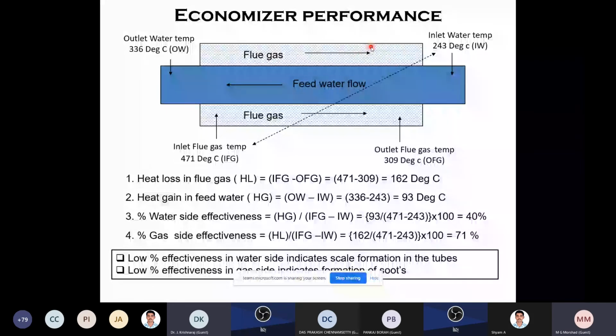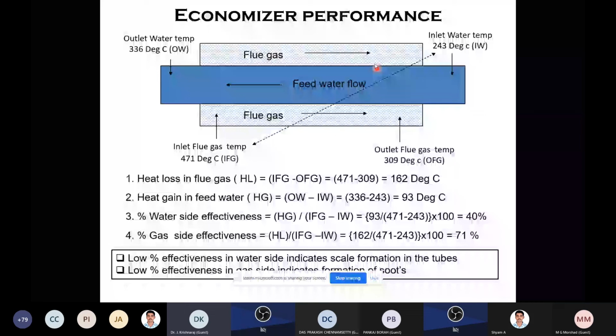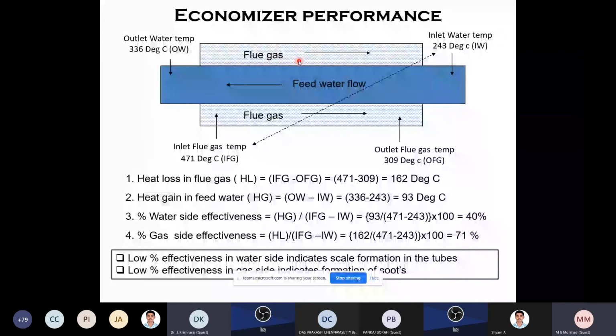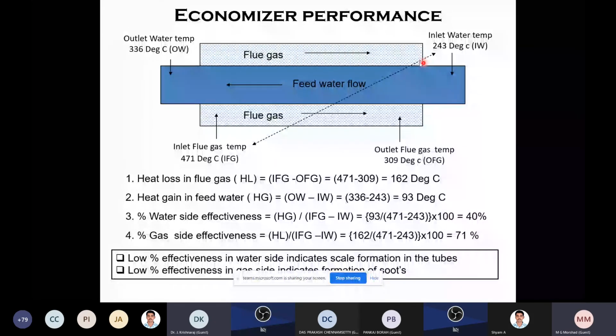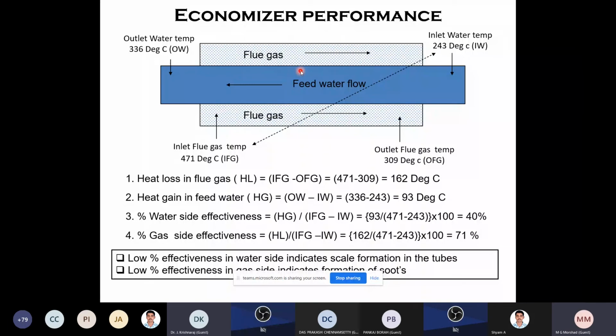This heat exchange between flue gas and the feed water depends on two things. One is the scale formation inside the water tube, or the soot formation outside on the gas side. So if the thickness of the soot is more, all the heat will not go through. Or if the scale formation in the pipe is more, the same happens. So one side is gas side effectiveness, another is water side effectiveness. Actually we calculate effectiveness depending on the heat head. Heat head is the maximum heat difference. See, this is the inlet temperature 243, the feed water inlet temperature and the inlet flue gas temperature.